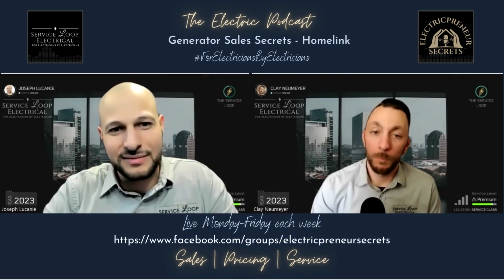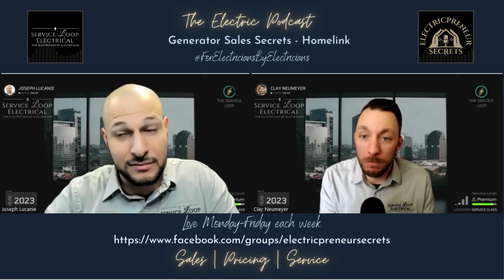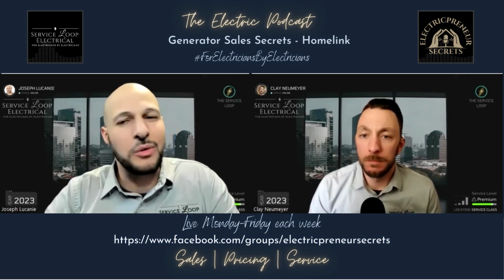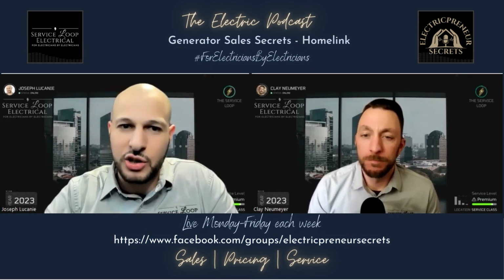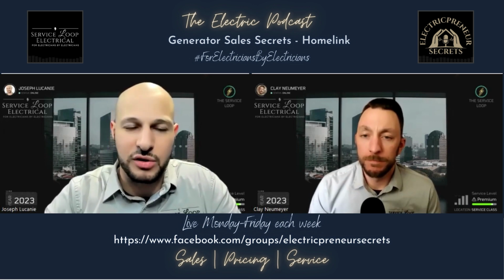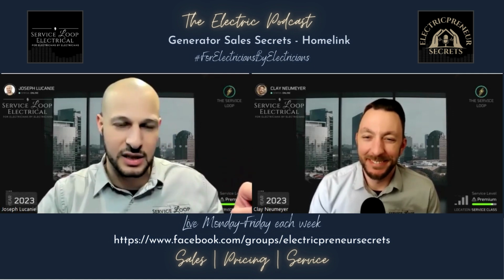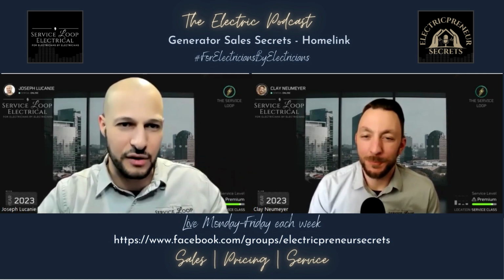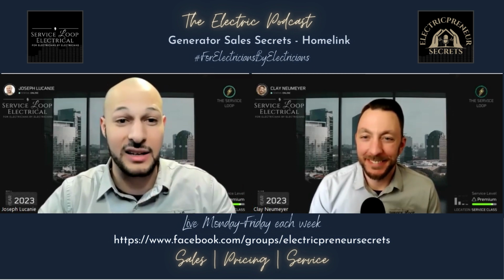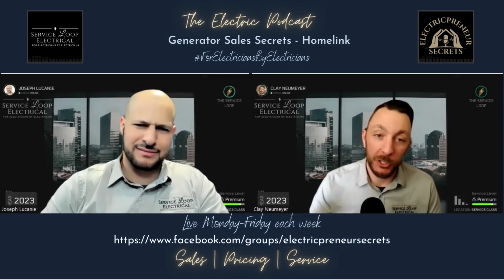Right. So neglecting the inlet for a second, the installation could be an hour, two? I would say realistically, to do an MTS effectively, an hour just doesn't feel like enough. Because I want to make sure that not only are we doing the circuits, but every time I would do an MTS, we would also do a whole home circuit labeling. Because if you're thinking about it, it says this is the furnace. But if I don't confirm this is the furnace and you lose power and the furnace doesn't come on, whose ass is on the line? Yeah, you're getting the call back. 100%. You got to confirm it anyway. To me, that's good commissioning.